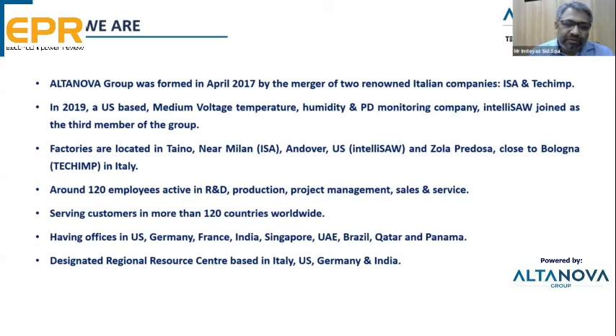Coming back to the different substation assets, for switchgear we have products and technology that help monitor the temperature and humidity of low voltage and medium voltage switchgear. Many times, if there is a loose connection or any kind of problem inside the panel box, unless the temperature starts increasing and we are able to monitor that, we will not get pre-information about the failure.